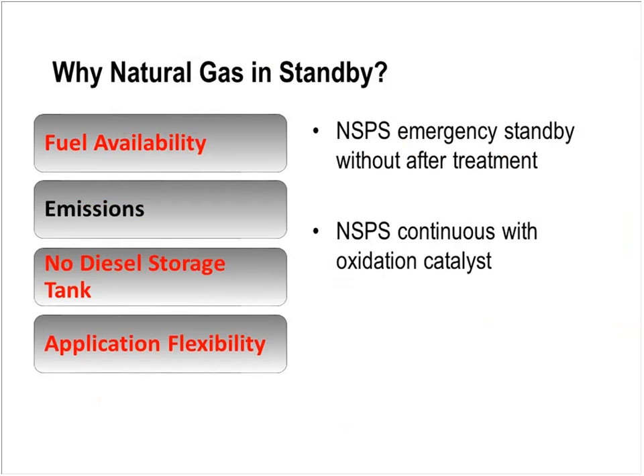From an emissions perspective, gas engines meet most of the new source performance standards requirements—that's the 2-gram level. But in some areas where there are requirements for lower emissions, you can do it with an engine with lower emission capabilities, at the risk of not having the same load acceptance. The lower the NOx level, the less fuel available to the engine immediately, which can make it more challenging on some load acceptance requirements.